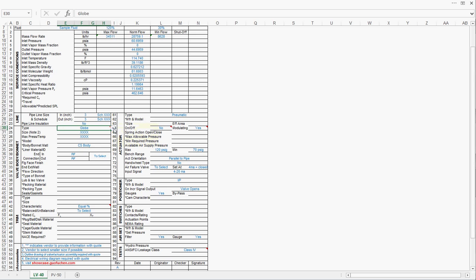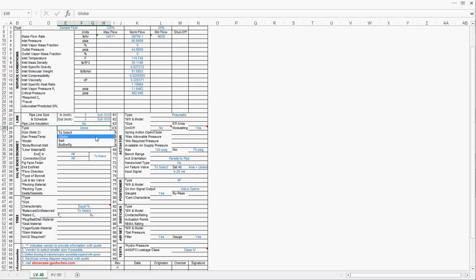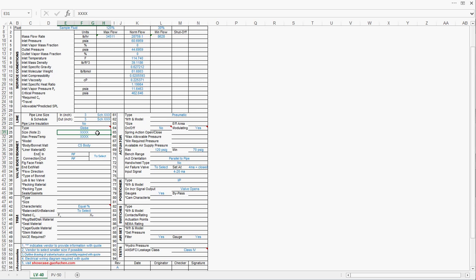Regarding the control valve types, generally there are three kinds: globe, ball, and butterfly. Globe valves are the most popular control valves type. Regarding the valve size, generally speaking, control valve is one size smaller than the pipeline size, hence here we are going to put two. However, it's always a good idea to verify with your vendors.